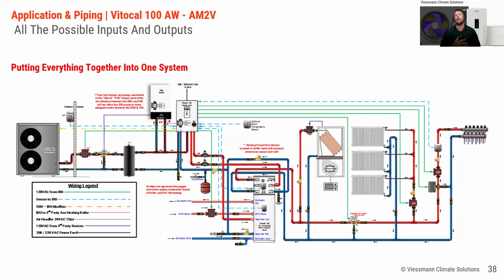Another one: can I use the same tank for cooling and heating? I see the buffer tank inside the package and assume it's not sized based on the minimum BTU requirement for a zone. The buffer tank that comes with the package is both a heating and cooling buffer tank. If you already have one on site, or you're setting up a system in, say, a cooling dominant market and pairing it with DHW, there is a possibility that tank might not be large enough, based on the flow rates and storage capacity, to operate, say, an air handler for the 20, 30, 45-minute turnaround, depending on what size tank and size unit you have.